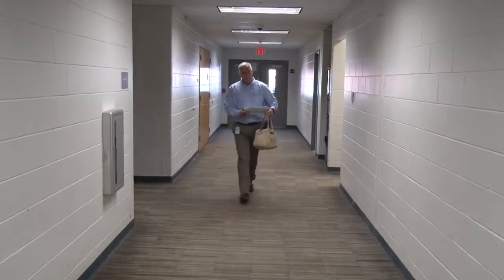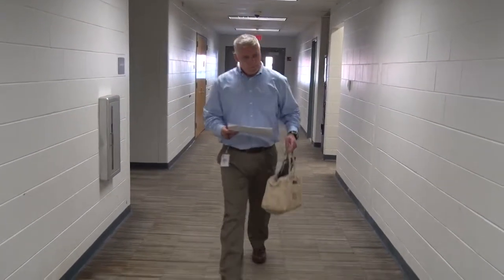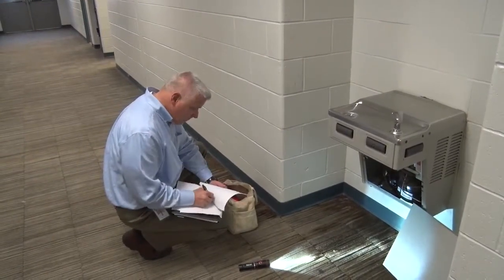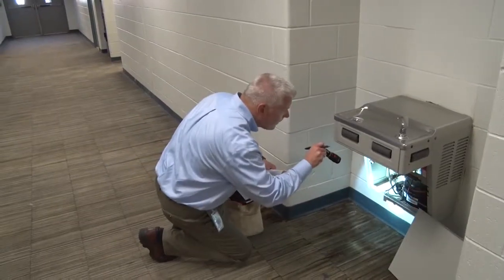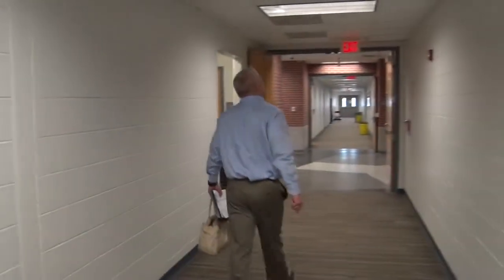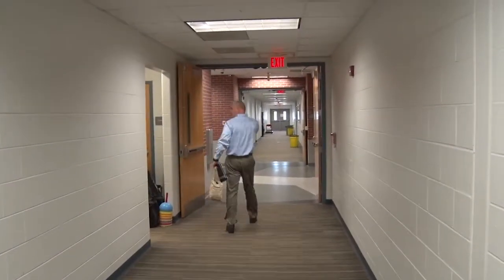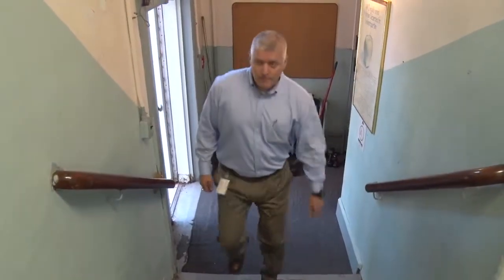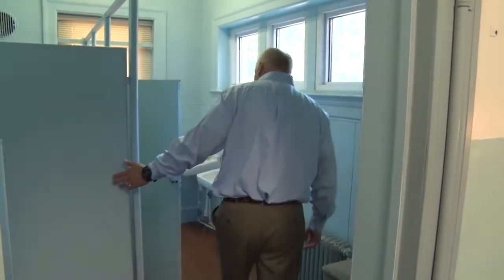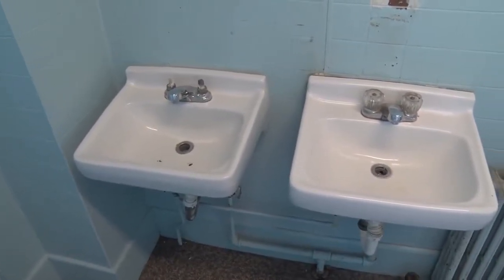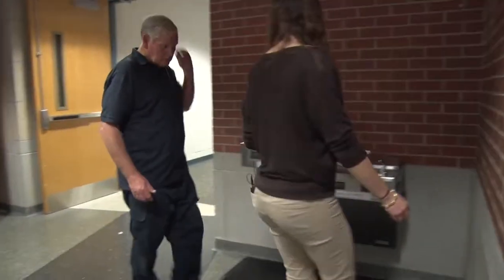The flow of cold water throughout the building can be determined during the walkthrough by following the cold water plumbing. For the drinking water outlet inventory, the walkthrough allows you to locate and verify all the drinking water outlets, conduct an assessment of the outlets, including if the assigned sample location ID code was correct, if the outlets are operational, if there are any signs of corrosion, such as leaking faucets or discolored water, if there are aerators or screens, or any other observations. Identify any outlets that are out of service and determine if there were any drinking water outlets missed initially from the inventory.